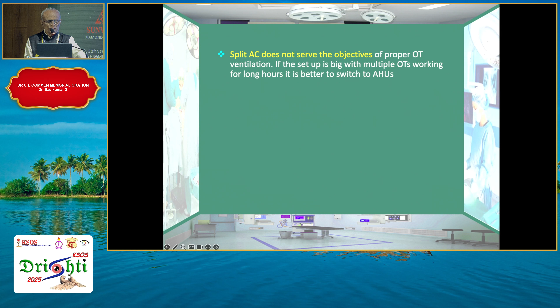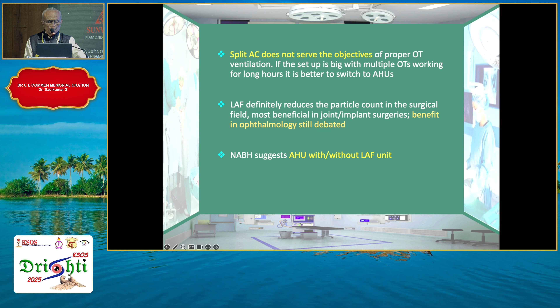Split AC does not serve the objectives of proper OT ventilation, and if the setup is big with multiple OTs working for long hours, it is better to switch to AHUs. The laminar airflow unit definitely reduces the particle count in the surgical field, which is most beneficial in orthopedic surgeries, but the benefit in ophthalmology is still debated. NABH suggests AHU with or without laminar airflow unit.